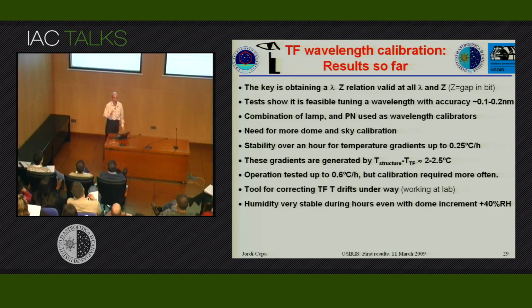So the stability against temperature is that you can work easily with temperature gradients up to 0.25 degrees per hour. That corresponds to a difference between the tunable filter and the telescope structure of about 2.5 degrees. That is quite high, which implies the standard operation of the telescope. And we tested the operation with a gradient of 0.6 degrees centigrade per hour successfully, but of course in this case you would need to calibrate often, about every half an hour or so, in order to check that there are no drifts.